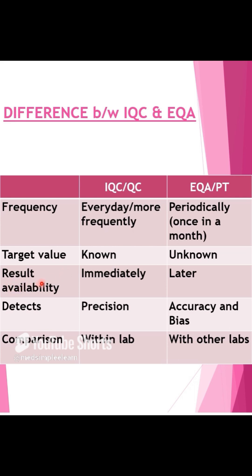The third basic difference is result availability. For IQC, results are available immediately within a few minutes, as IQC is mainly a tool for day-to-day monitoring of laboratory performance. While EQA results are available later, because EQA is a tool for long-term assessment of laboratory performance. IQC basically detects precision and short-term accuracy of results, whereas EQA gives an idea of long-term accuracy and bias.